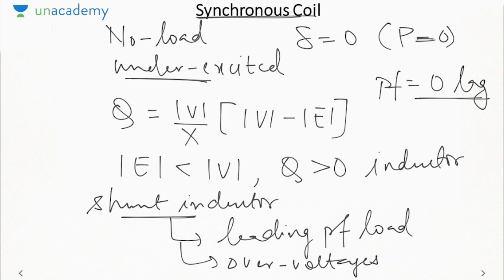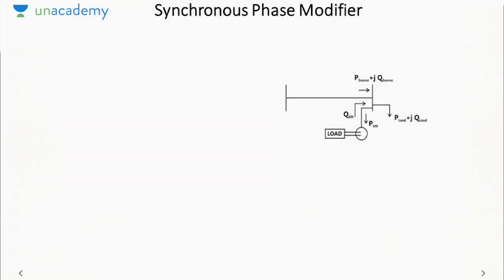Okay, but remember this point: the terms synchronous motor and synchronous condenser and synchronous coil are both defined in reference to the no load condition. There should be no load at the shaft of the machine. Next method of dynamic voltage control is called the synchronous phase modifier.